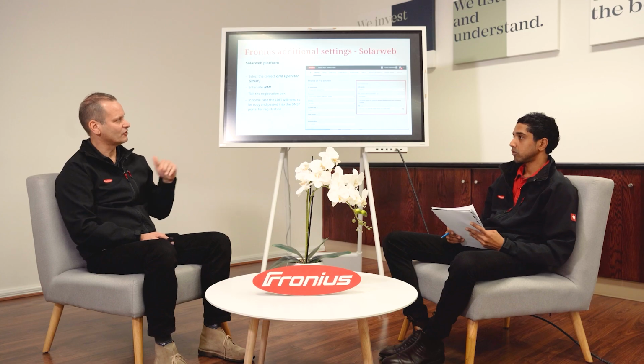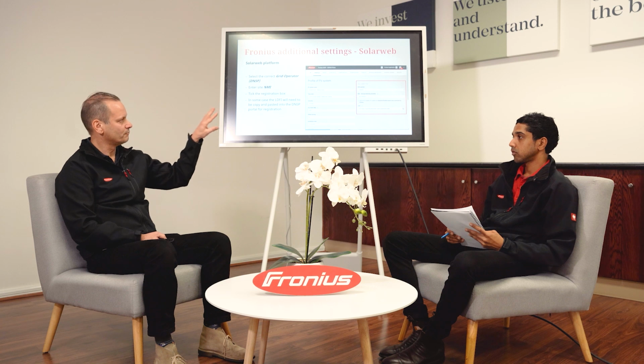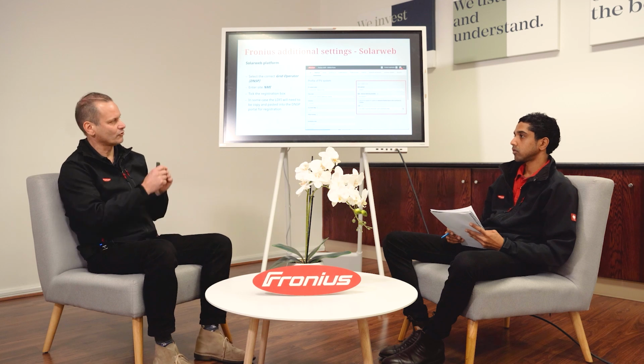So everyone except for Gemini will have what they call in-band registration, meaning that once you put in your NMI and select the DNSP and hit save, that'll automatically register that device. It'll create that long number, register it, send it to the DNSP and register it, and things like that. Even though it'll show up in Solar.web, you don't need to do anything with that number.